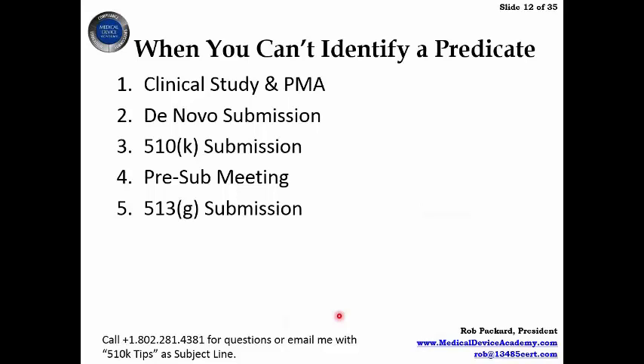That's likely to end up one of 2 ways. You're either going to get an RTA letter, so they'll decide within 15 days that no thank you, it's not going to fly. That actually would be a good thing because the response in 15 days is only a 15-day delay. The worst case scenario there would be you get a non-substantial equivalence letter at about 130 days after you've provided a whole bunch of additional information. And they tell you, now we think you ought to go the de novo route or go the PMA route, when you could have just gone the de novo route or the PMA route right from the beginning. So hopefully you haven't wasted too much time with the Hail Mary pass, but sometimes it's worth it.